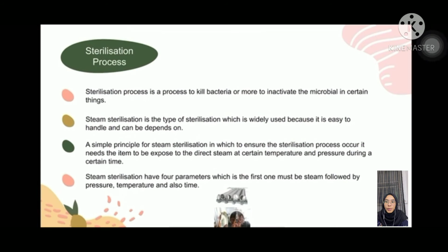The simple principle of steam sterilization is that, to ensure the sterilization process occurs, the item needs to be exposed to direct steam at a certain temperature and pressure during a certain time. So steam sterilization has four parameters which we need to focus on. The first one, obviously, is the steam. Second is the pressure, third the temperature, and also the time.